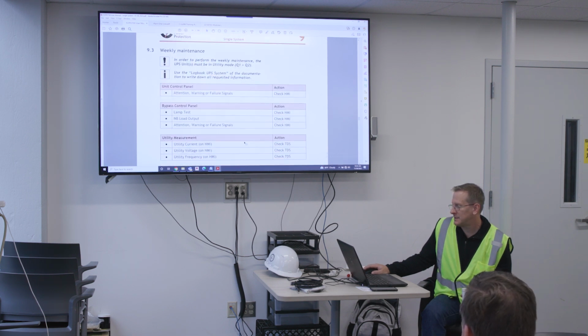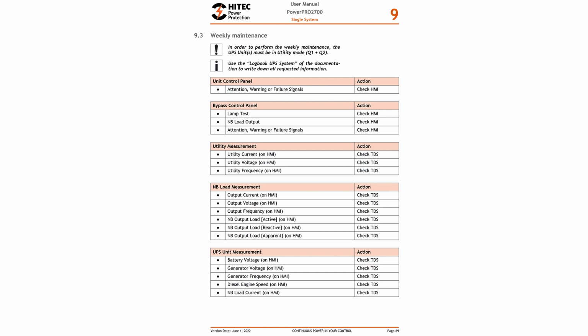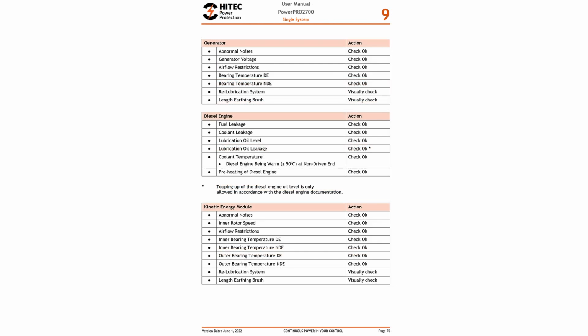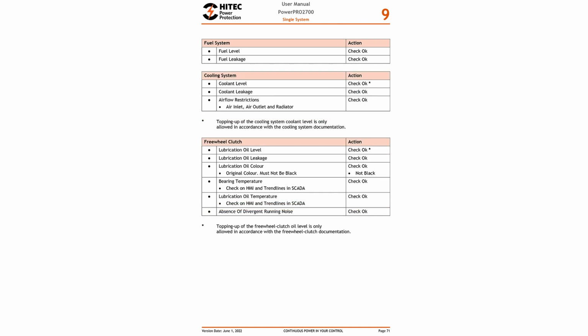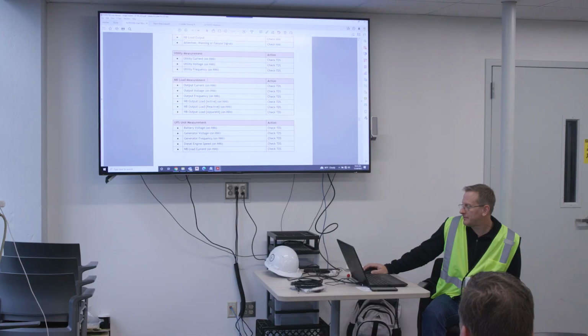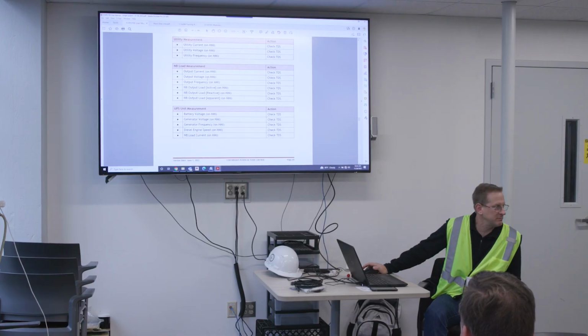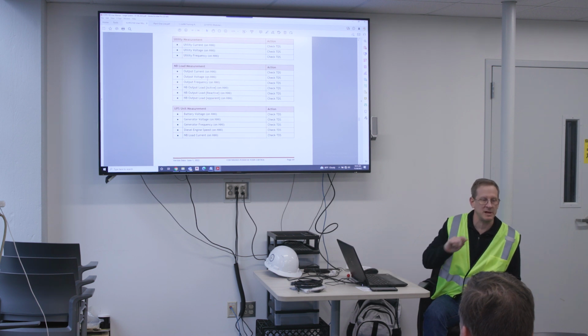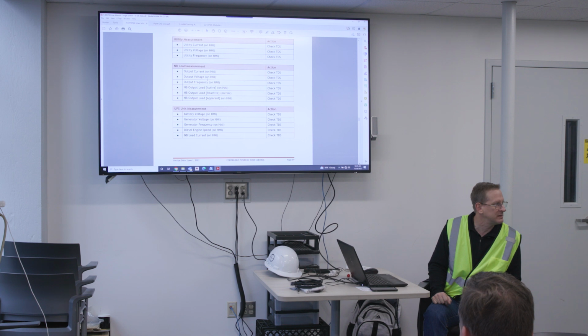So those are your dailies. Here are some of your weeklies. A little more involved, of course, as you'd expect. Again, all the same checks as your dailies. You don't have a bypass control panel, so don't worry about that. But do a lamp test of your HMI, make sure all your bulbs are working. Look at your output voltages and frequencies to make sure they're where you expect them to be. Look at your power levels and your currents. Basically, this is most of the things you can find on the HMI, so it's just a quick scan through your HMI screens to make sure everything is good.